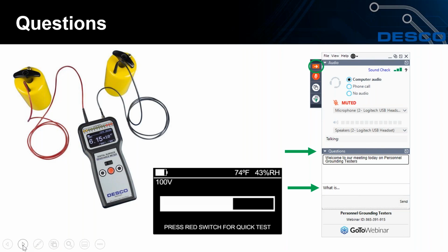If I'm doing qualification, as an example, for testing some materials, I need to check at 12% and 50% humidity. So I'm going to need to control that, and I can confirm with my tester that I'm in those ranges that I need to be. But normally for regular compliance verification, it's not a factor unless I have a failure.